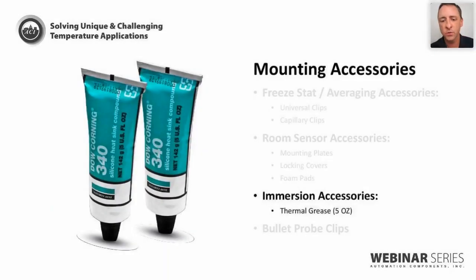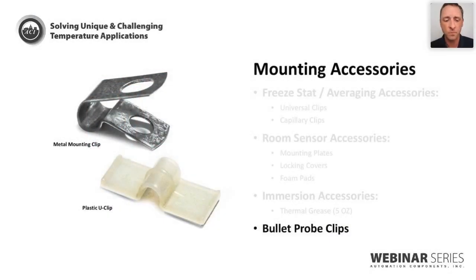For our immersion sensors, as well as our StrapOn sensors and the pipe mount sensors, we have two different types of thermal compound or heat sink compound, both a silicon-based and a non-silicon-based grease. For our bullet probes, we have two very inexpensive, simple ways to mount bullet probes, and these are kind of a universal solution to very cost-effectively install bullet probes. They can be attached to a duct, to a grate covering a damper, or numerous different applications where you want a cost-effective and fast way to get your temperature sensor installed.